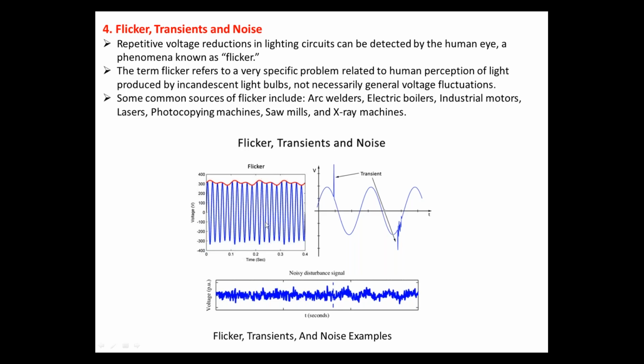You can see a blue sinusoidal waveform of the voltage, but the red color shows the flickers, meaning voltage drops, a very small variation in amplitude, not a straight line. Ideally it should be straight, but instead the amplitude of each cycle of this AC sinusoidal waveform is unstable, showing variation. These variations are due to sudden operation of devices like arc welding, electric boilers, industrial motors, photocopying machines, mills, which draw very high current for a moment, resulting in flicker of the voltage, clearly observed in this sinusoidal waveform.